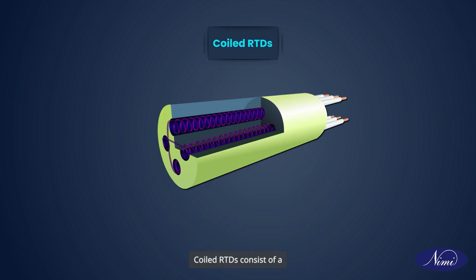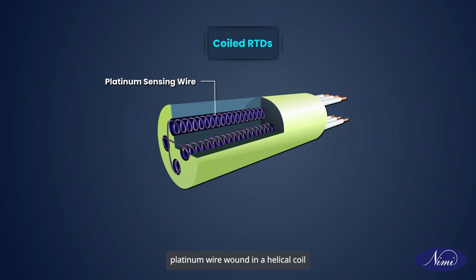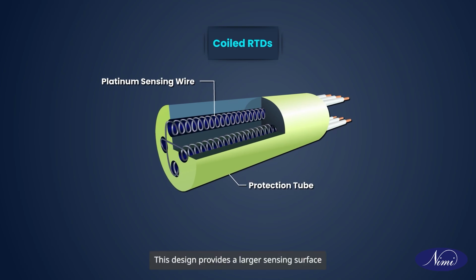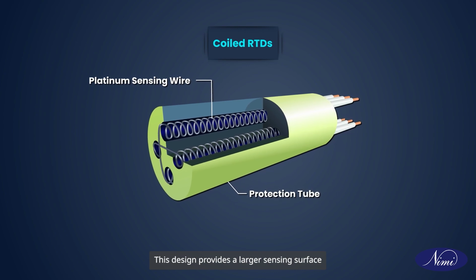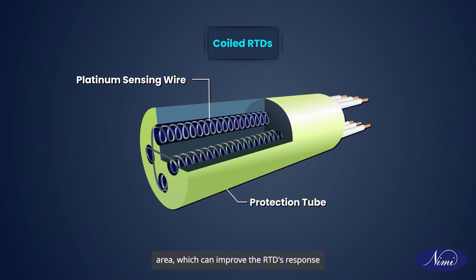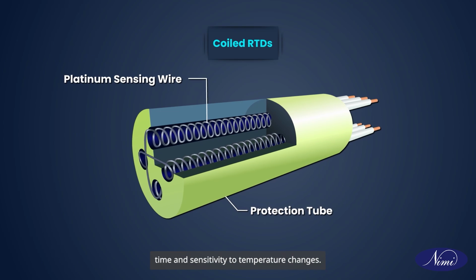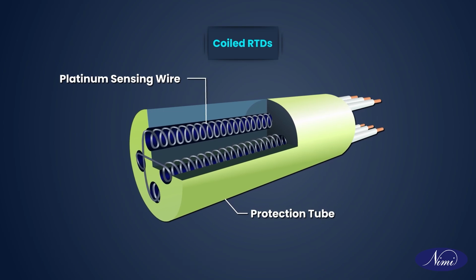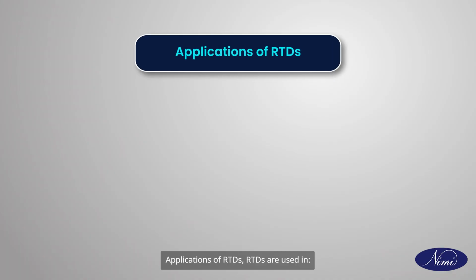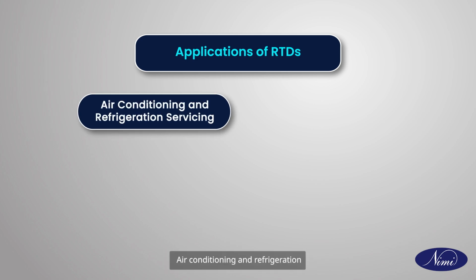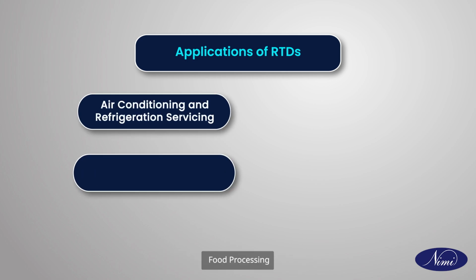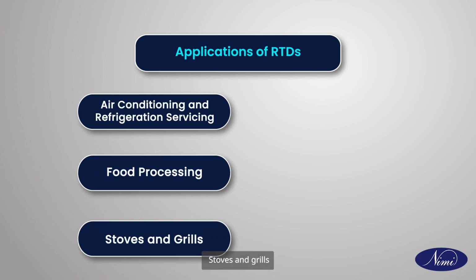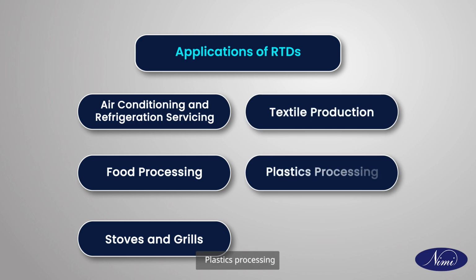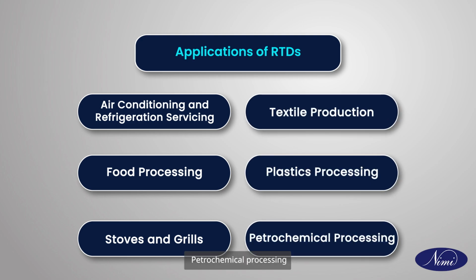Coiled RTDs. Coiled RTDs consist of a platinum wire wound in a helical coil pattern around a ceramic or glass core. This design provides a larger sensing surface area, which can improve the RTD's response time and sensitivity to temperature changes. Applications of RTDs. RTDs are used in air conditioning and refrigeration servicing, food processing, stoves and grills, textile production, plastics processing, and petrochemical processing.